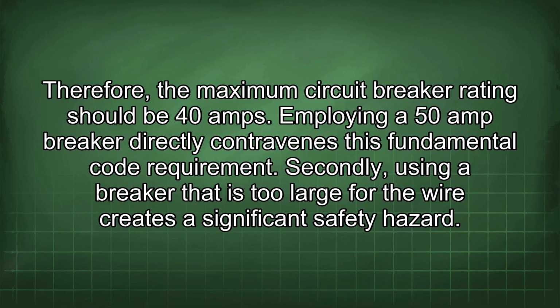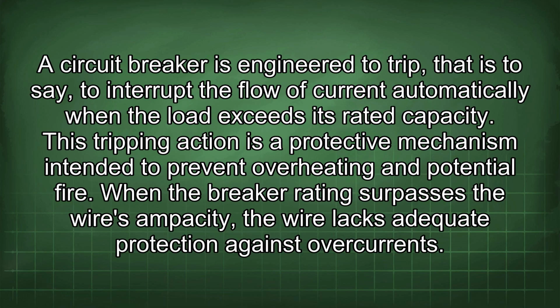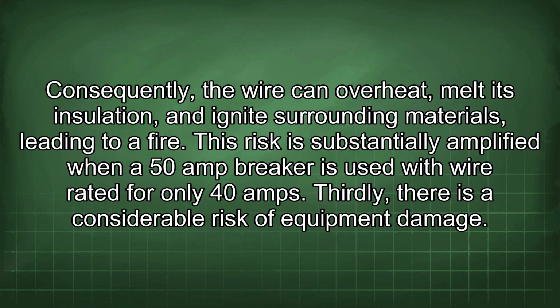Secondly, using a breaker that is too large for the wire creates a significant safety hazard. A circuit breaker is engineered to trip, that is to say, to interrupt the flow of current automatically when the load exceeds its rated capacity. This tripping action is a protective mechanism intended to prevent overheating and potential fire. When the breaker rating surpasses the wire's ampacity, the wire lacks adequate protection against overcurrents. Consequently, the wire can overheat, melt its insulation, and ignite surrounding materials, leading to a fire. This risk is substantially amplified when a 50 amp breaker is used with wire rated for only 40 amps.